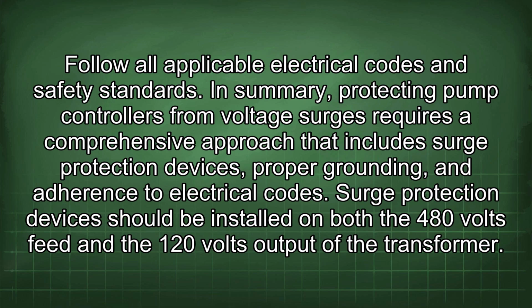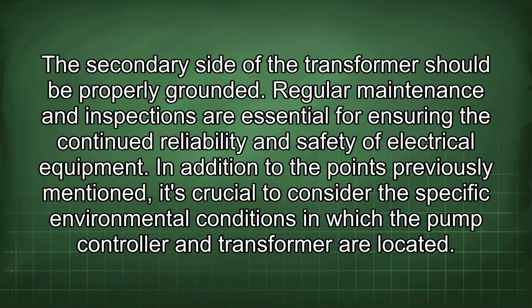In summary, protecting pump controllers from voltage surges requires a comprehensive approach that includes surge protection devices, proper grounding, and adherence to electrical codes. Surge protection devices should be installed on both the 480 volt feed and the 120 volt output of the transformer. The secondary side of the transformer should be properly grounded. Regular maintenance and inspections are essential for ensuring the continued reliability and safety of electrical equipment. In addition to the points previously mentioned, it's crucial to consider the specific environmental conditions in which the pump controller and transformer are located.